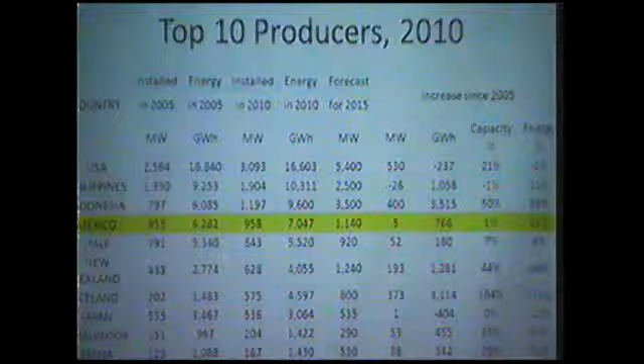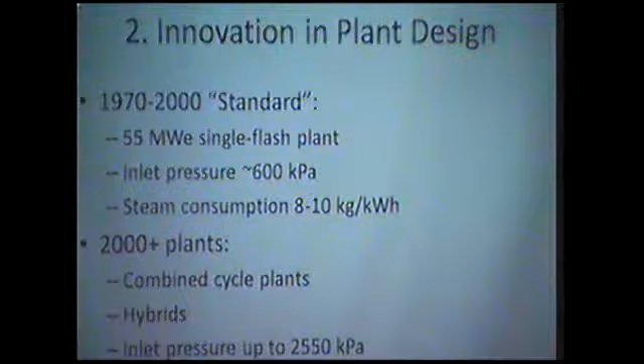A typical geothermal power plant for the last 40 to 50 years has had a specific steam consumption in the range of 8 to 10 kilograms per kilowatt hour of generated electricity. Over the last 10 to 15 years, however, we've had a lot of technical innovation in power plants themselves, using, for example, combined cycle plants that are hybrids of geothermal and other sources, and a much more significant range of inlet pressure. Most of the old plants have more or less the same design, but in some newer examples, steam consumption is as low as 5 kilograms per kilowatt hour compared to 8 to 10 previously. So they're almost twice as efficient.